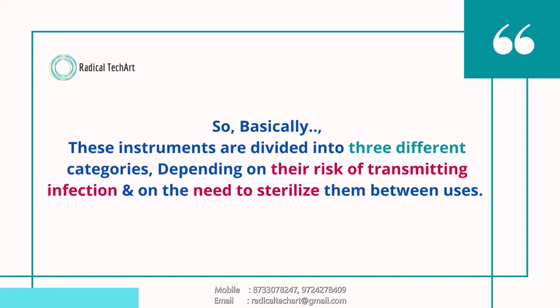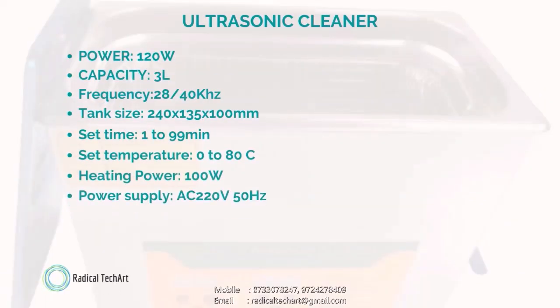It is clearly visible that there is no trouble using ultrasonic cleaners in dental applications. These instruments are divided into three different categories depending on the risk of transmitting infection and the need to sterilize them between uses. The technical specifications of the ultrasonic cleaner are: power 120 watt, capacity 3 liters, frequency 28 to 40 kilohertz, tank size 240 by 135 by 100 mm, set time 1 to 99 minutes, set temperature 0 to 80 degrees centigrade, heating power 100 watt, power supply AC 220 volt 50 hertz.